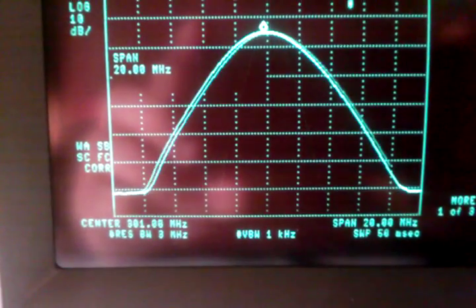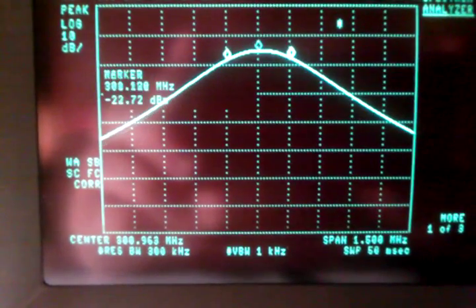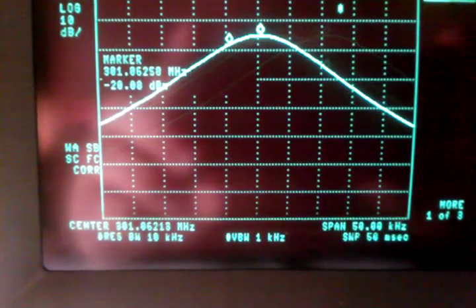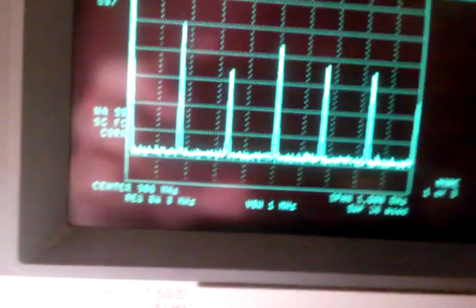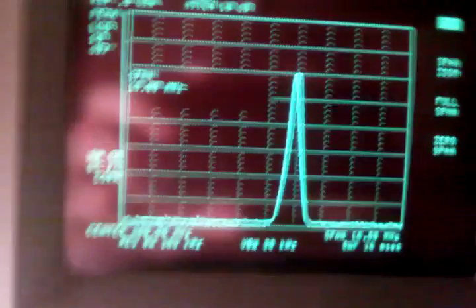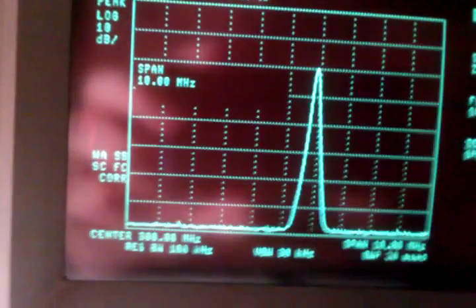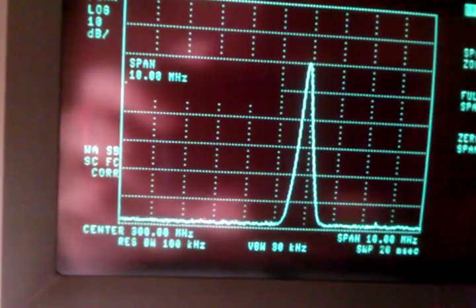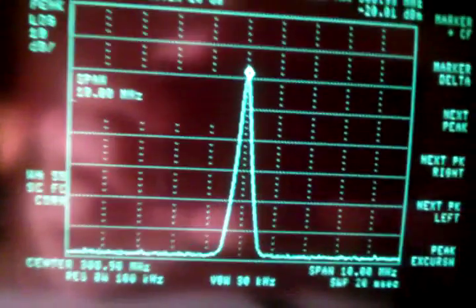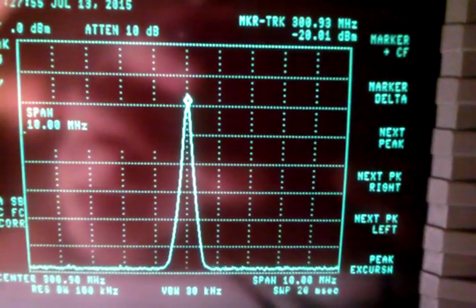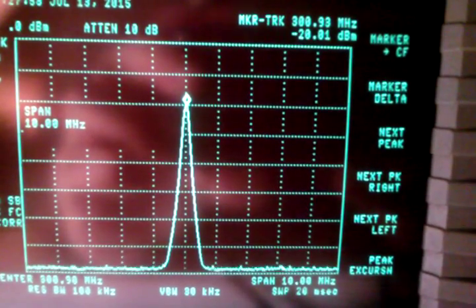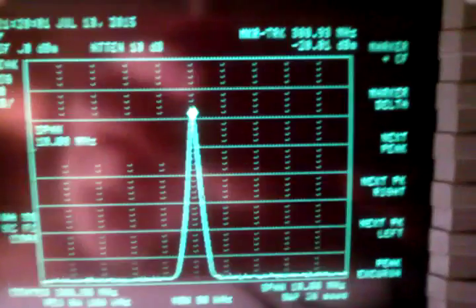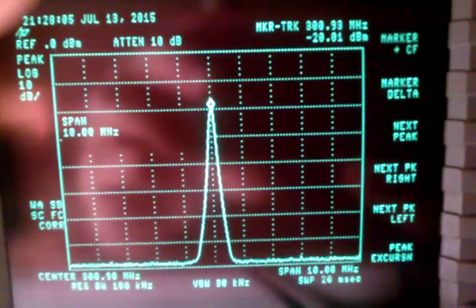And this is using those new correction coefficients. And as you can tell, it passed. And now we will preset again. Set the center frequency for 300 megahertz. The span for 10 megahertz. And there we go. Peak search, peak, peak, and then peak search. And we're basically at 300.9 and negative 20 dBm. So the amplitude is pretty much perfect.